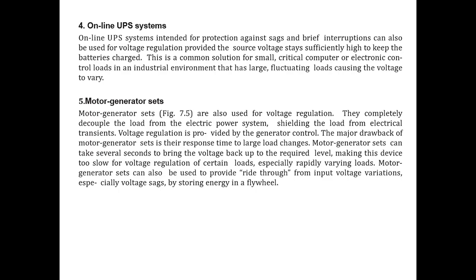We can also use a motor generator set. Motor generator sets are also used for voltage regulation. They completely decouple the load from the electric power system, shielding the load from electrical transients. Voltage regulation is provided by the generator control, and the major drawback of the motor generator set is its response time to large load changes. Motor generator sets can take several seconds to bring the voltage back to the required level.